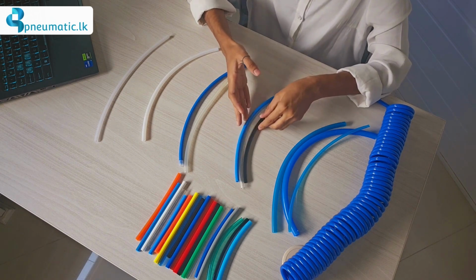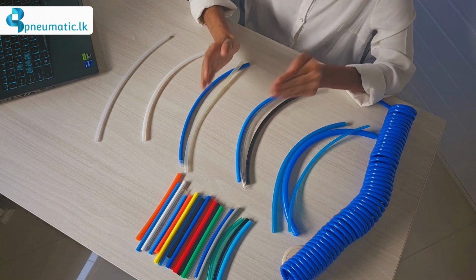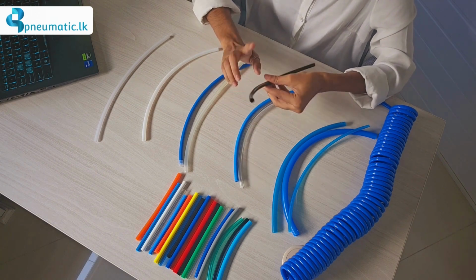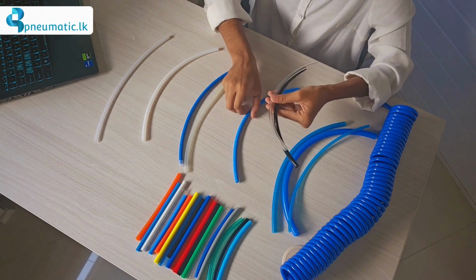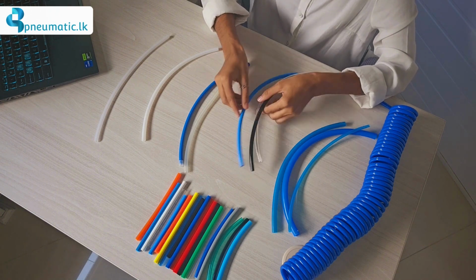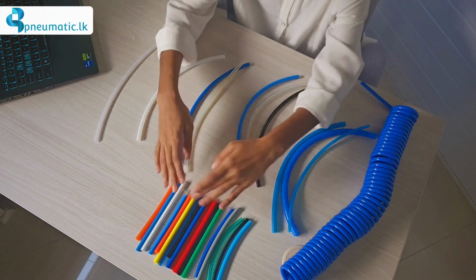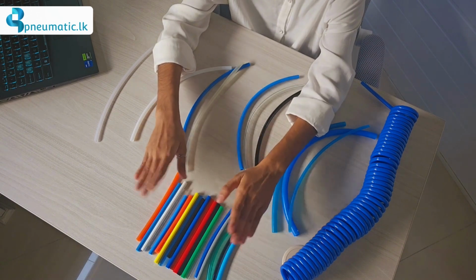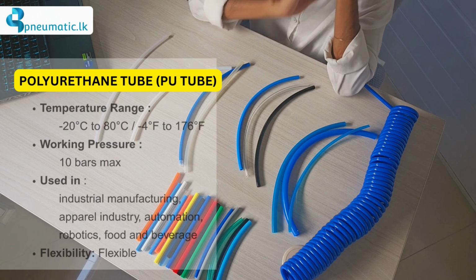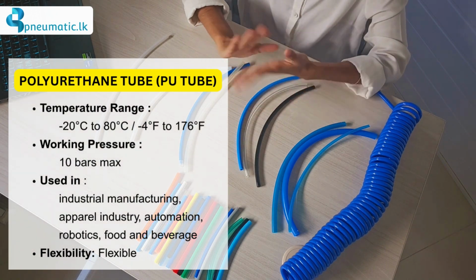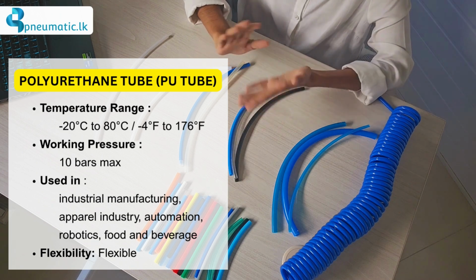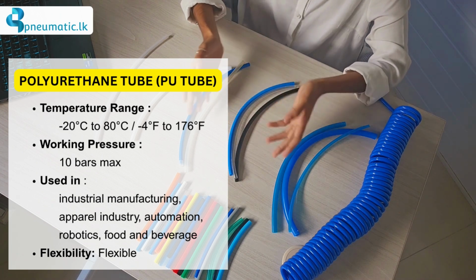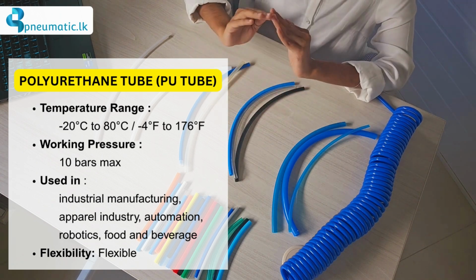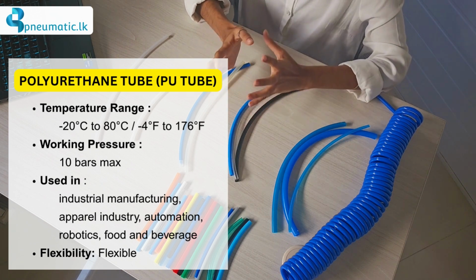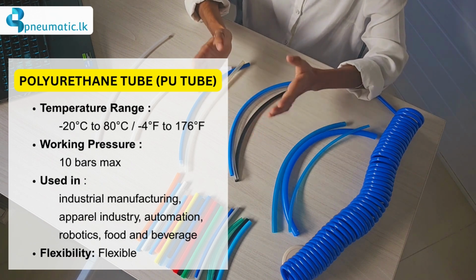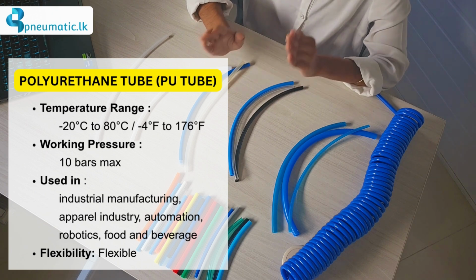So PU tubes, polyurethane tubes, you can find in different colors. Here you can see a black color, then this is transparent, then this is blue, and not only that, you can see PU tubes in other colors as well. Polyurethane tubings also provide pressure resistance. It can handle 10 bars, whether you are transporting compressed air, water, or chemicals. The temperature this can handle is minus 20 Celsius to plus 80 Celsius.